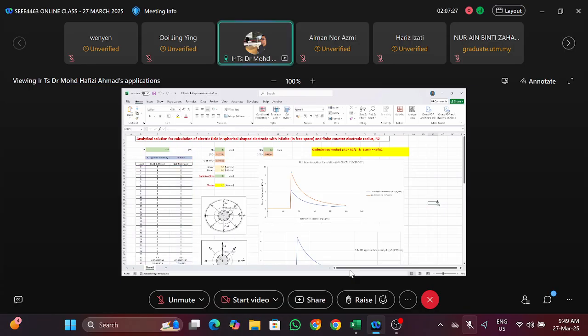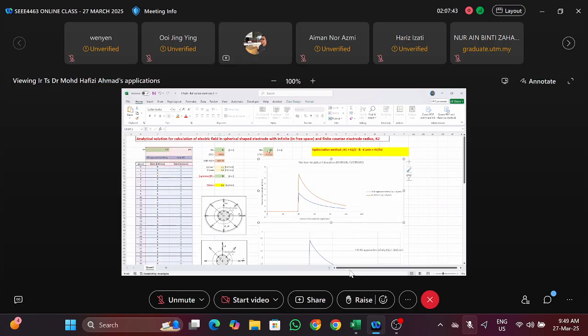I have two options. Either I increase the radii, let's say I use 80 here and 40 here, and now you can see the electric field will reduce. Or I need to use different insulation materials. I cannot use gas; I need to use a better insulation, either solid or liquid.